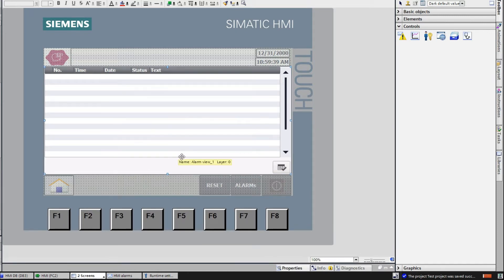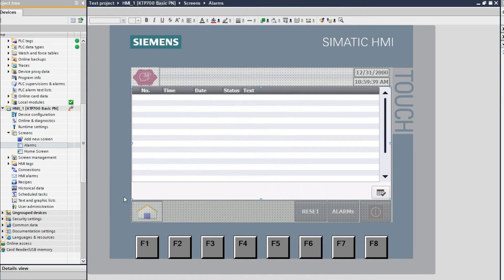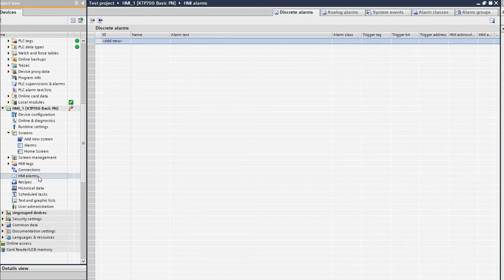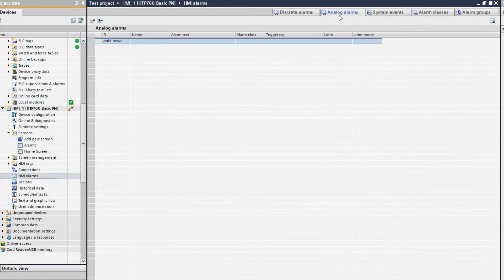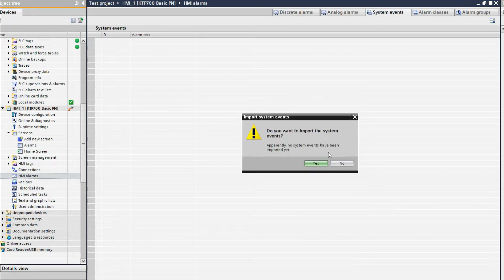This is the alarm viewer setting. Now you have to configure the alarm. To configure the alarm, go to the HMI alarm by double-clicking. It will open that window. Here you can see some buttons: discrete alarm, which is a digital alarm generated by a binary tag; analog alarm, which generates an alarm from an analog value; and system event, which shows events of the PLC or HMI.